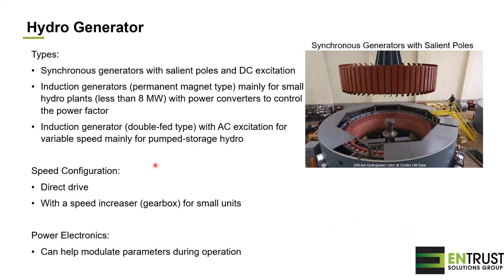We can have different kinds of configuration. Most of the time it's a direct drive with the runner, but for smaller projects where the runner goes at high speed, we will need a speed increaser, with a gearbox for smaller units to generate the electricity, not a speed decreaser, but increaser. Sorry. And all of this, more and more, the power electronics is important to modulate the parameters during operation.